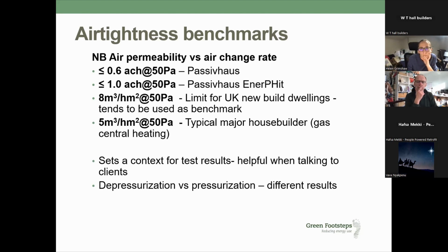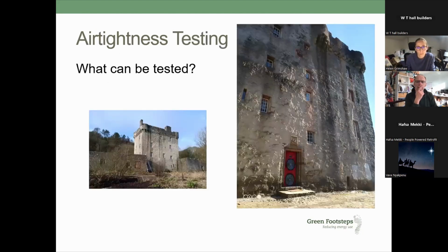Here's a good photograph. You can test most things. This is a job that I did earlier this year. It was built in 1503, and interestingly, the airtightness of this castle came out as substantially more airtight than the 2007 building that I tested the day before.